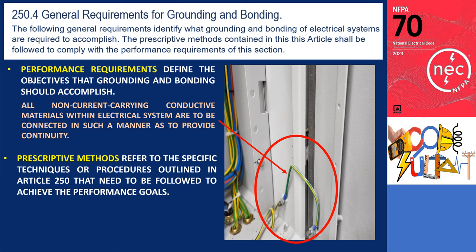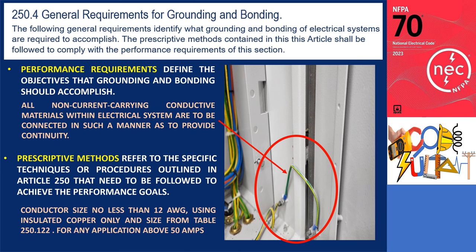For example, a prescriptive method mandates that all metal enclosures should be bonded using an insulated copper conductor of at least 12 AWG, as specified in Table 250.122, for any application above 50 amperes.